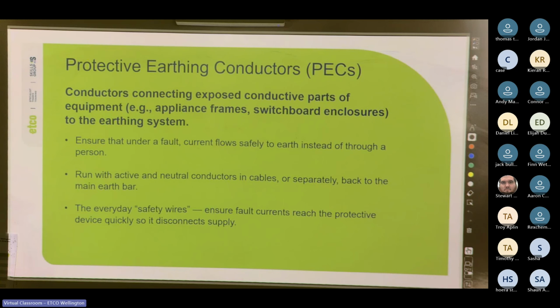So we run it with the active and neutral conductors in our cables. According to the wiring rules, it is supposed to be in the center of the cable. The reason for this is if you hit the cable from any one point, you're going to hit either neutral-earth or phase-earth. So you're always putting the earth in the middle to protect ourselves.